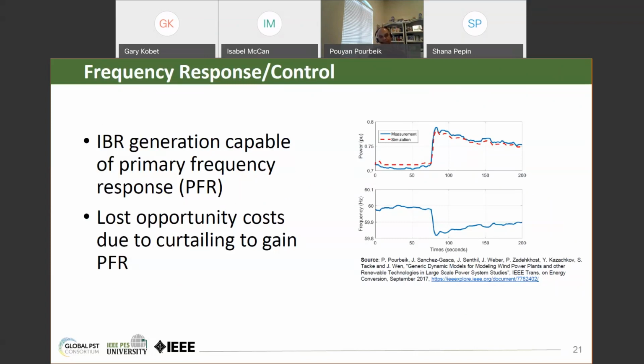There is lost opportunity cost associated with providing under frequency response, or in other words, providing frequency response when the system frequency drops, particularly in the case of wind and photovoltaic generation. Let's explain that. Let's assume we have a wind power plant, and that at this point in time there's enough wind incident on our plant for us to produce 100 megawatts of power. Well, we want to produce 100 megawatts, because if we don't, we lose that opportunity, because that wind may not be there an hour from now or 2 hours from now. So we want to produce as much power as we can at this point in time.